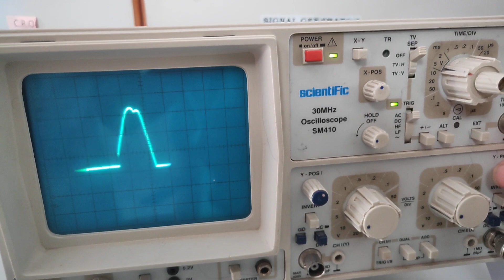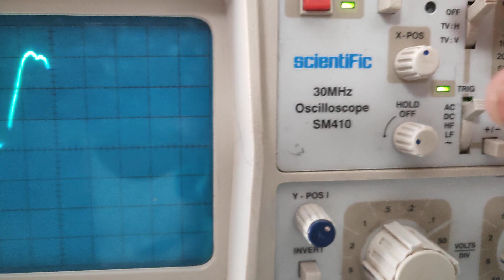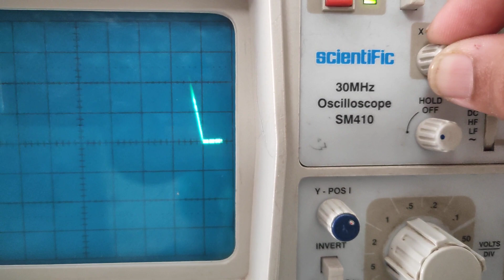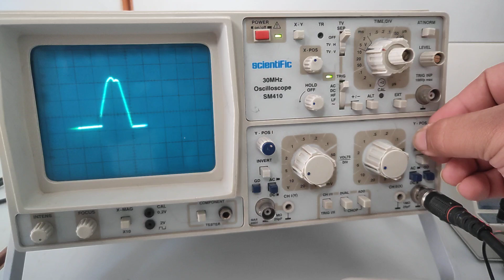At times it may be shifted like this, and then you will get a false firing angle. You should make sure the end of the positive cycle coincides with the vertical line. Right now it's still 18 degrees. To get the correct firing angle, vary the X position of the wave so you know the actual correct angle. Now we will vary the DRB to get 36 degrees.